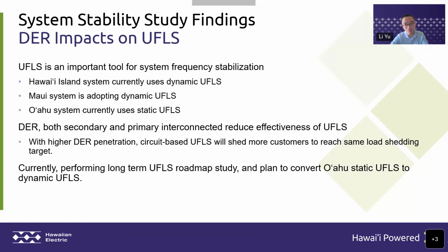And in our system stability study for an extreme scenario, we do see that we originally targeted an underfrequency load shedding system with around 300 megawatts of load available for shedding, and after assuming all the DER forecast can be realized in the future years, we only got around 80 megawatts of net load in this toolbox. So we are currently addressing this issue. Under the commission's order, we're doing a long-term underfrequency load shedding roadmap study right now, and we also have a plan to convert Oahu's static underfrequency load shedding scheme to a dynamic one. Next slide, please.